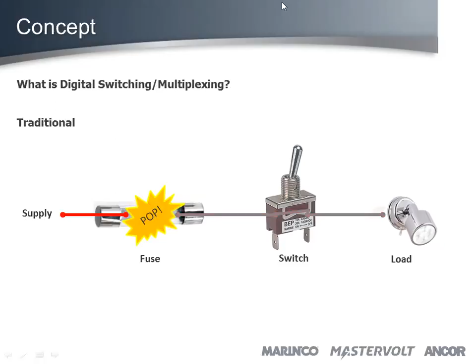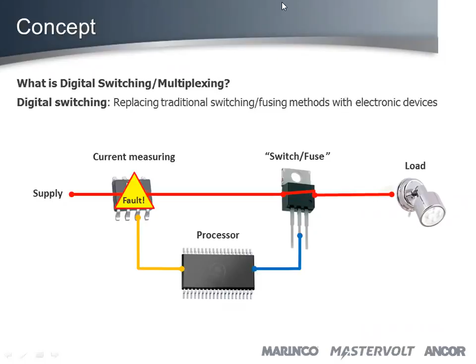Digital switching, you have a current measurement device, an electronic or solid state contactor, what we call it, and a microprocessor monitoring and controlling all this. So it detects a fault, that signal goes to the processor, which controls the MOSFET and opens it up.